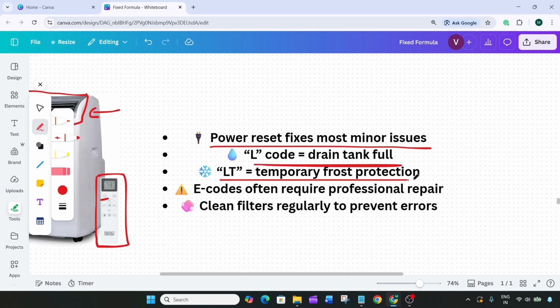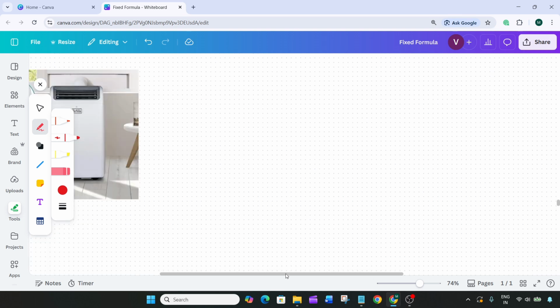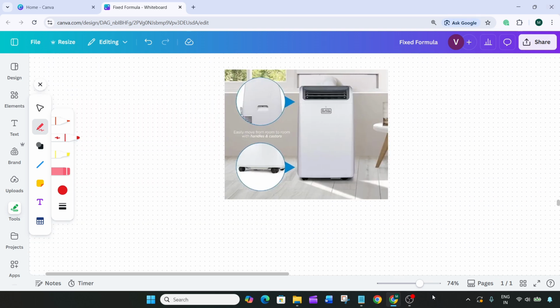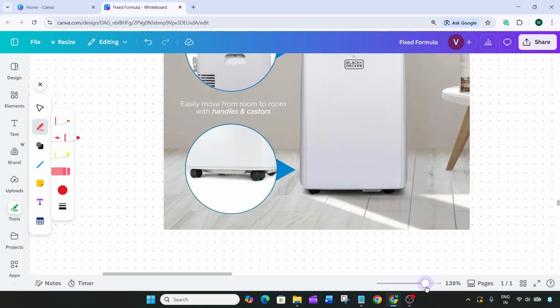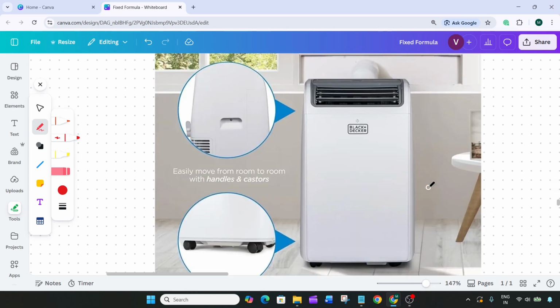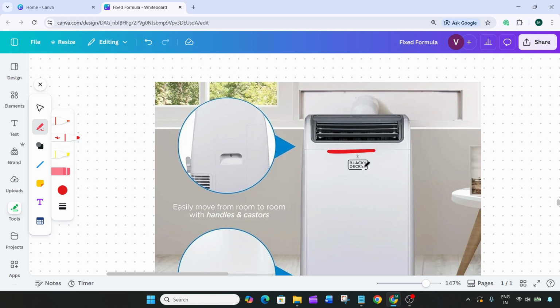If resetting doesn't fix the issue, check the display for error codes. These codes help identify specific problems. A code like L usually means the water tank is full and needs draining. LT indicates low temperature protection, which prevents frost buildup and should clear automatically. PF points to a temperature probe issue.